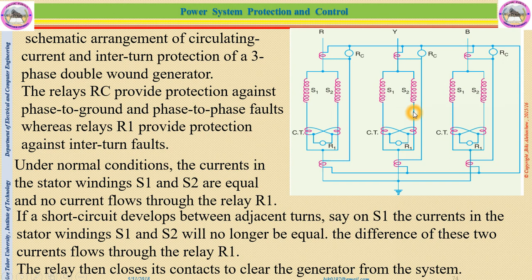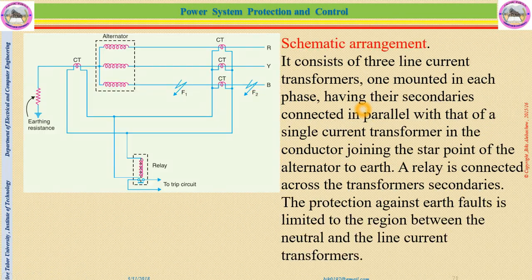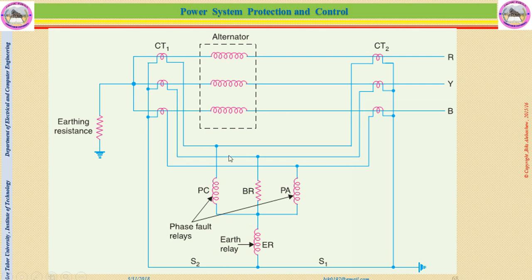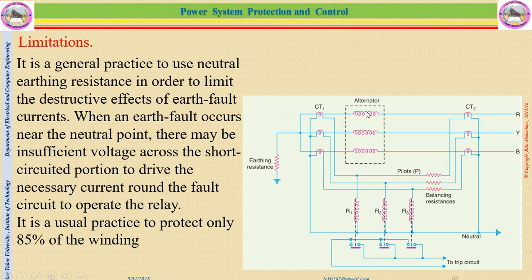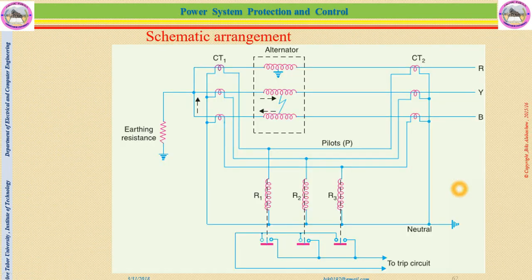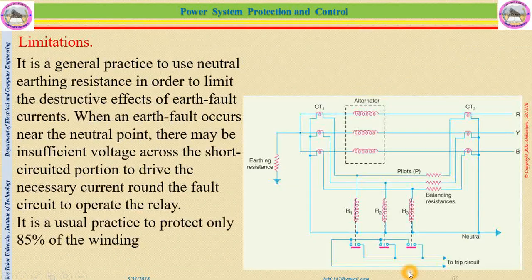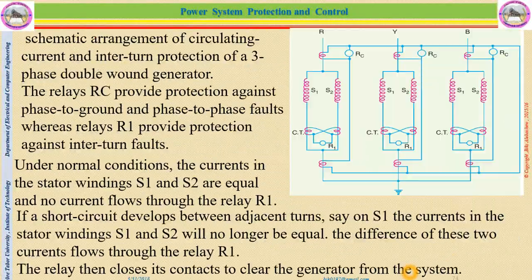So this arrangement contains two things. One is the differential protection, this section. This one is similar to the previous one, you can see from the previous one. They are already inverted. The only difference is that one. So this has two protections. One is circulating current protection, and the other one is interturn protection. The interturn protection is this one. R1 is the interturn relay, and RC is here. You can see RC is the circulating current relay.